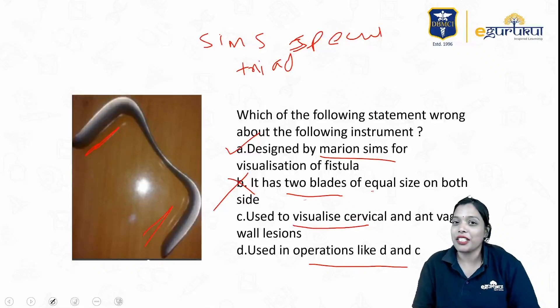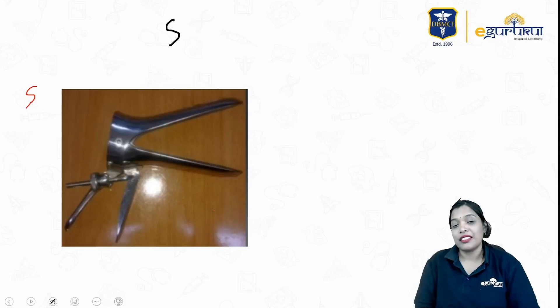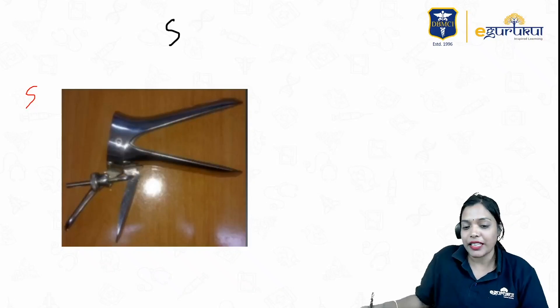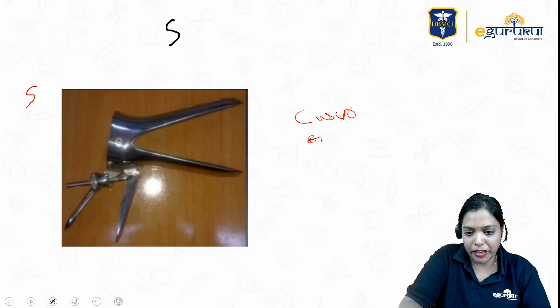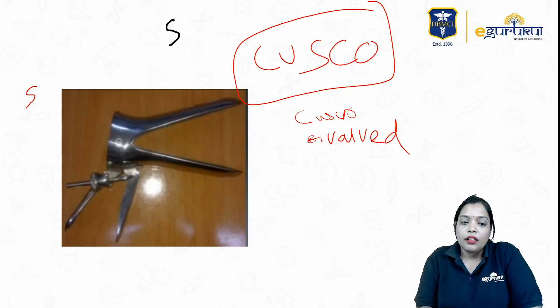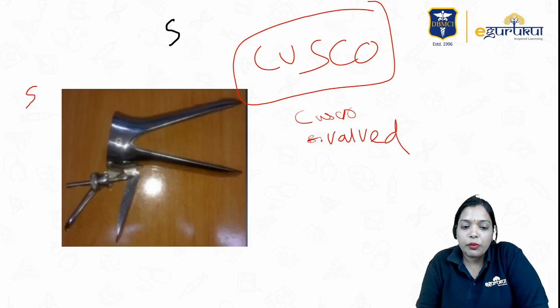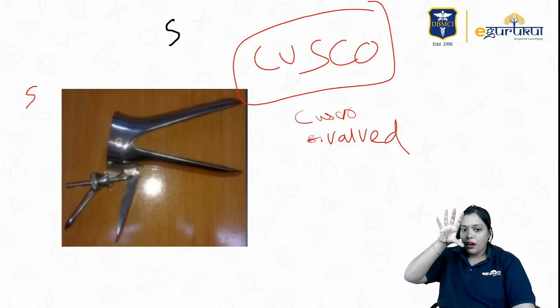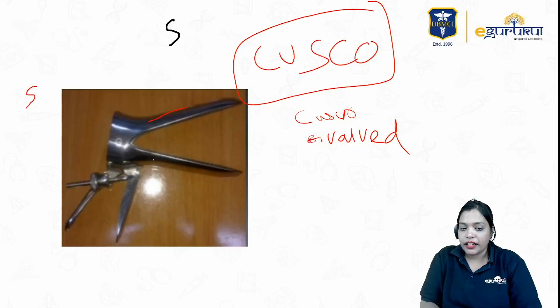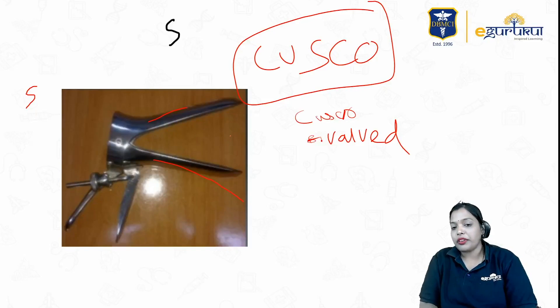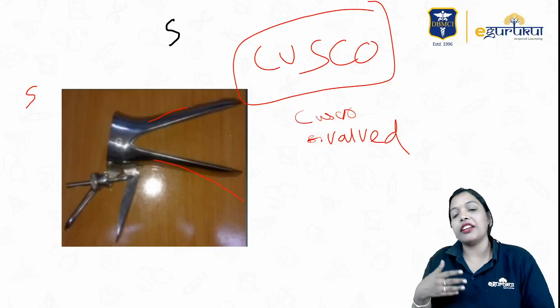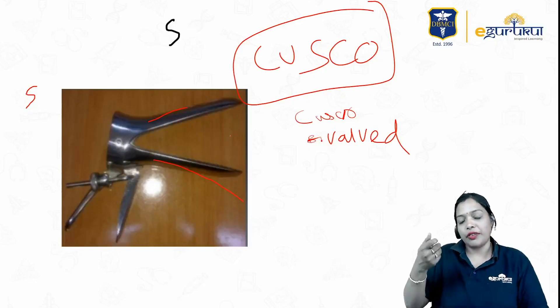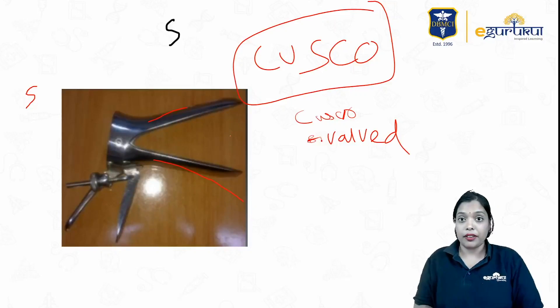Another speculum commonly used in gynecological procedures is the Cusco's self-retaining bivalve speculum. It is a self-retaining speculum — you have a knob that you can tighten. Both blades retract the anterior and posterior vaginal wall, allowing you to visualize the cervix, take a biopsy, insert a copper T, or take a Pap smear. You don't require anyone to hold it; just fix the screw.